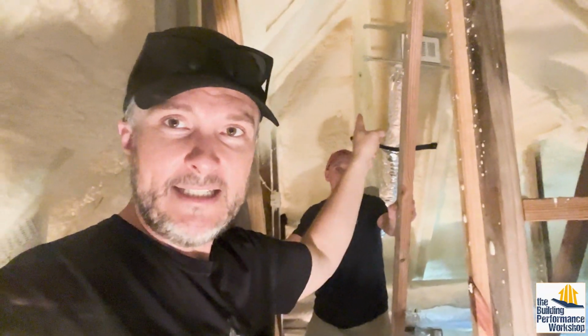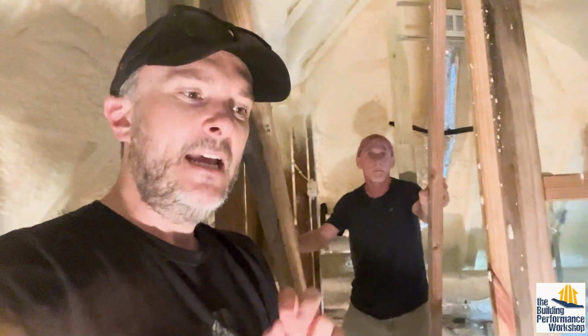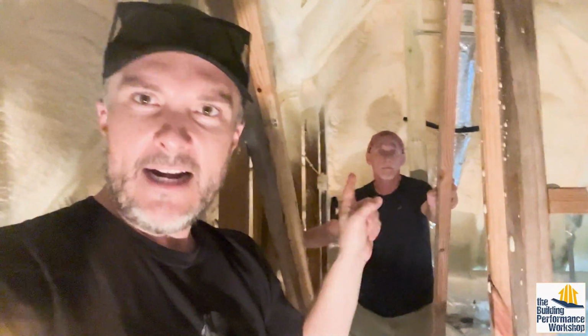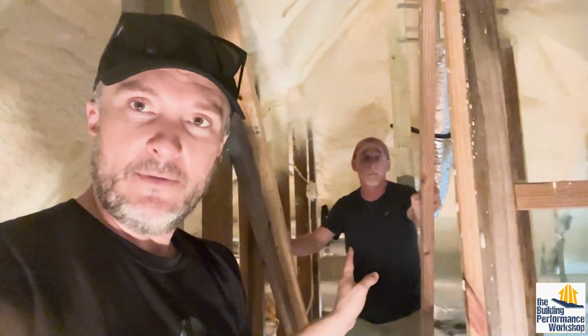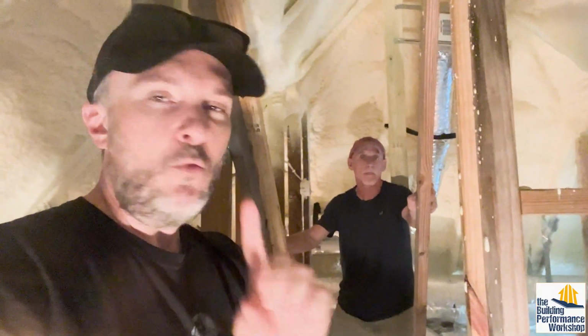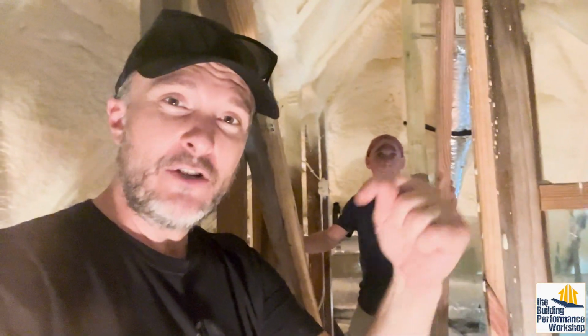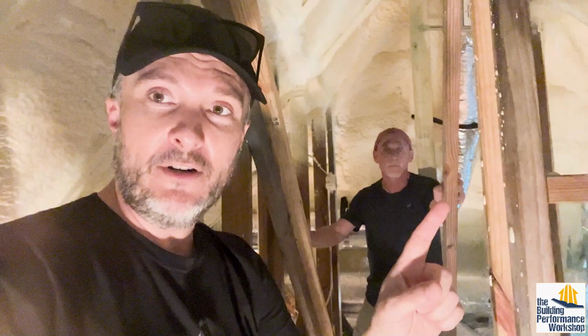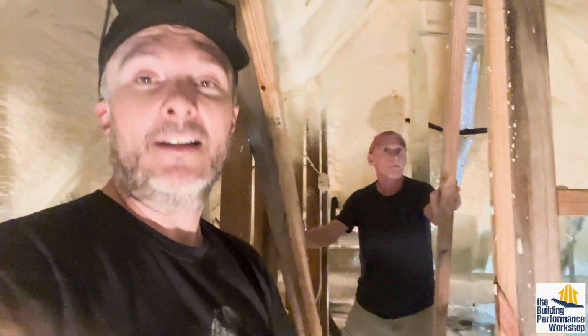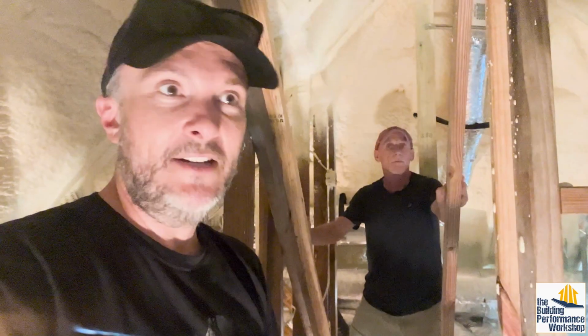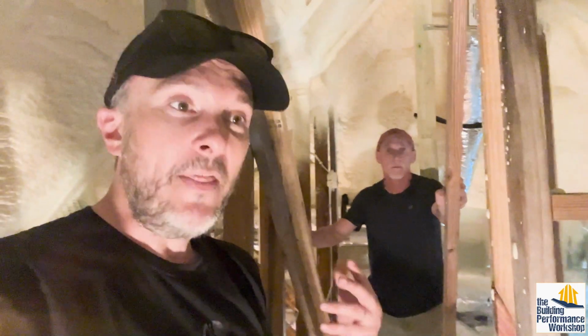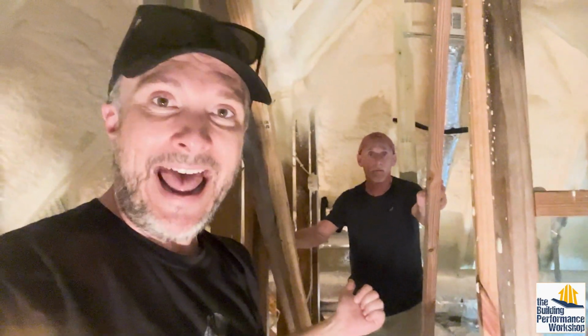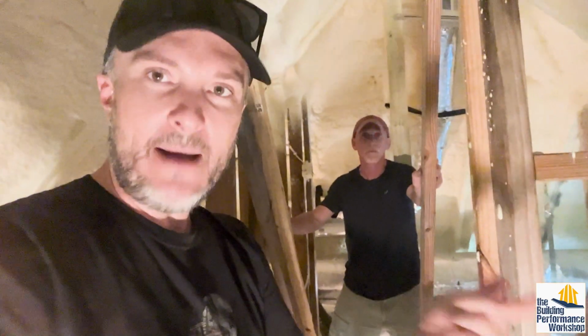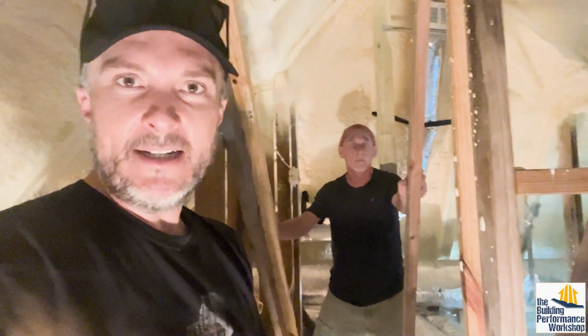So just before anybody does this, returns from the attic, calling it a conditioned space and assuming the air will come up from below, that kind of approach can depressurize the attic, which may increase your air infiltration from outside if the spray foam job isn't perfect. But as you can see, Mark really QC'd this job, looked over every inch, and made sure there weren't any holes. Obviously, we're going to test this too. But if he finds out he does need to add some supply air to the attic, he can always just pop a grill into one of these supply ducts up here.